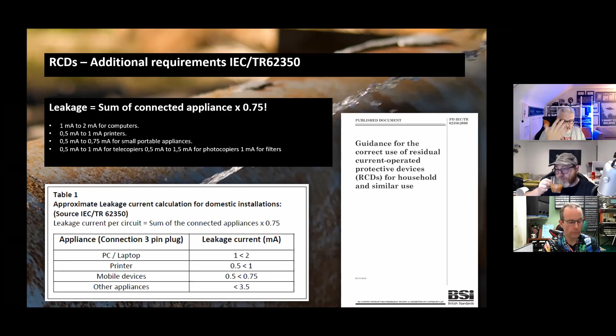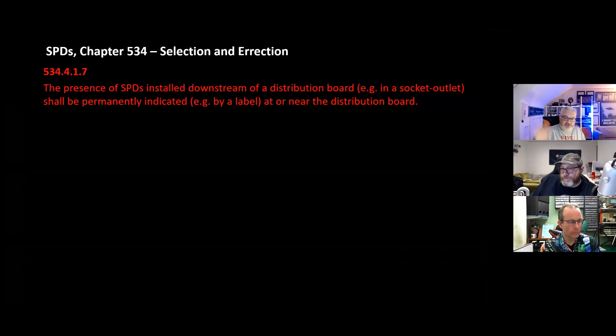Very quickly now, the last bit in chapter 5, 534.4.1.7, there is a requirement for a label of a surge protection device. It was the presence of surge protection devices installed downstream of a distribution board, potentially type 2s or type 3s, i.e. in a socket outlet, shall be permanently indicated by a label at or near the distribution board. That has now been rewritten. It now says the presence of surge protection devices in an installation shall be indicated by a label at or near the distribution board. The label shall also include instructions for checking the status indicator of the SPD. The requirements of this regulation need not be applied for domestic household premises or simple installations where fixing the label is not reasonably practicable.